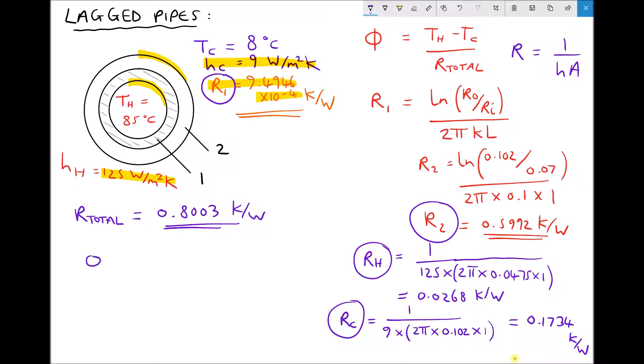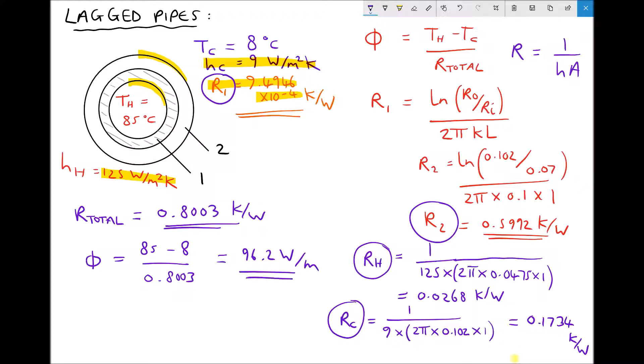The rate of heat transfer per metre of length equals the hot temperature of 85 minus the cold temperature of 8, divided by 0.8003, which comes out to be 96.2 watts per metre, accurate to 1 decimal place. Notice that this is lower than the previous value where we had thinner insulation and didn't include the surface heat transfer coefficients. With thicker lagging we can reduce the amount of heat loss as expected, and by including our surface heat transfer effects we also see a slight reduction in the rate of heat transfer from the hot fluid to the surrounding air.